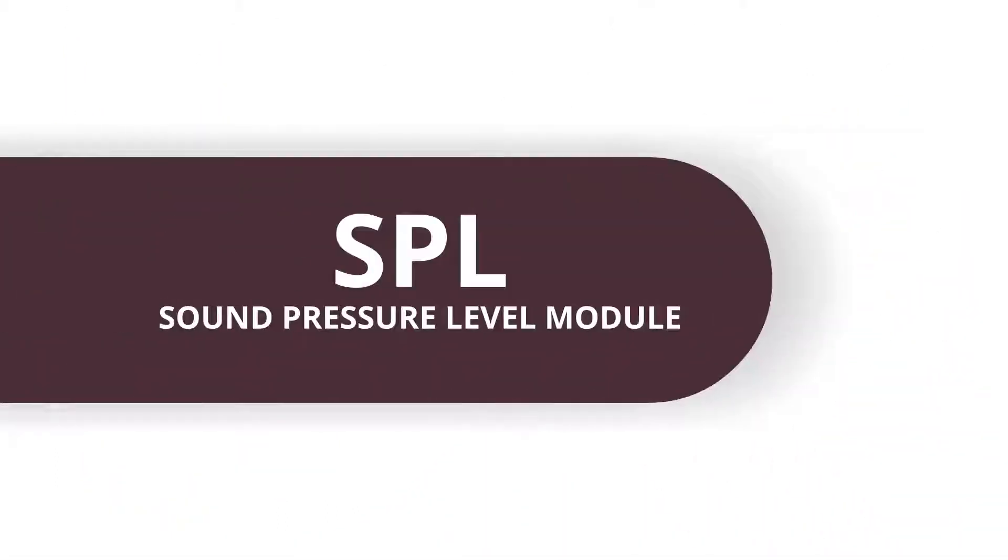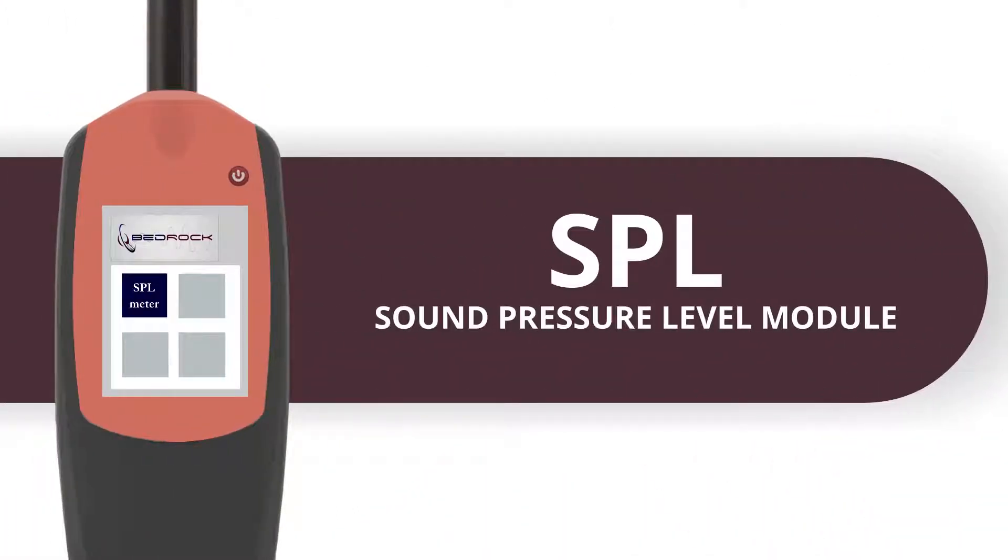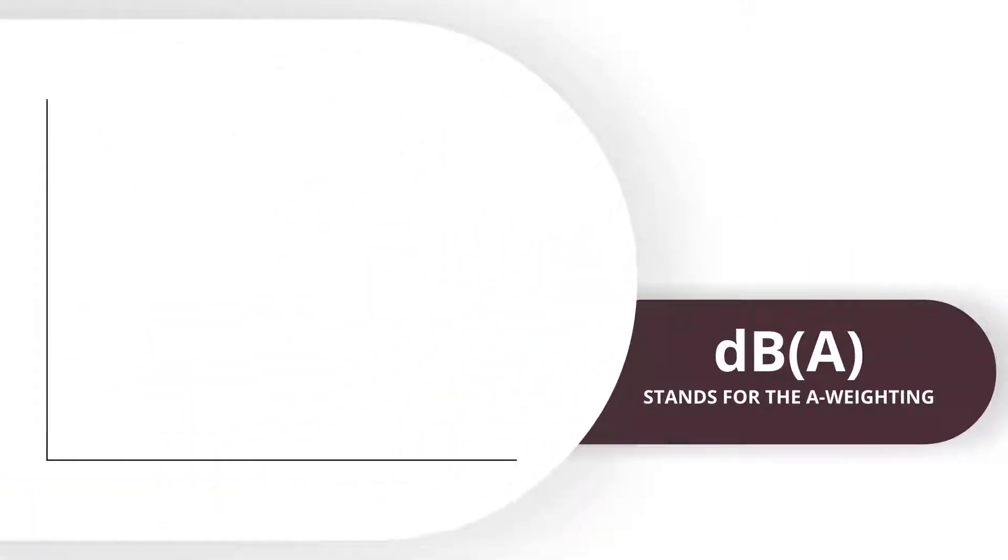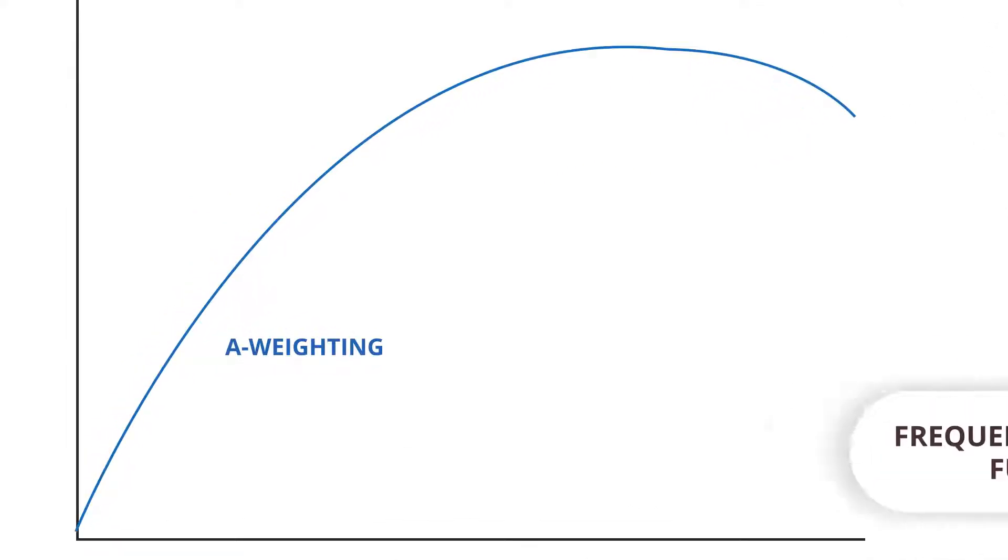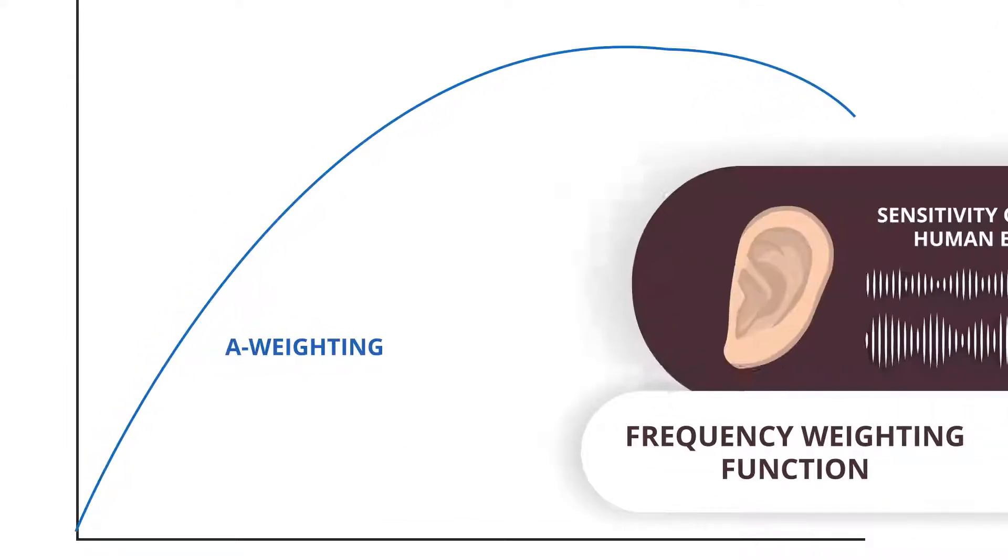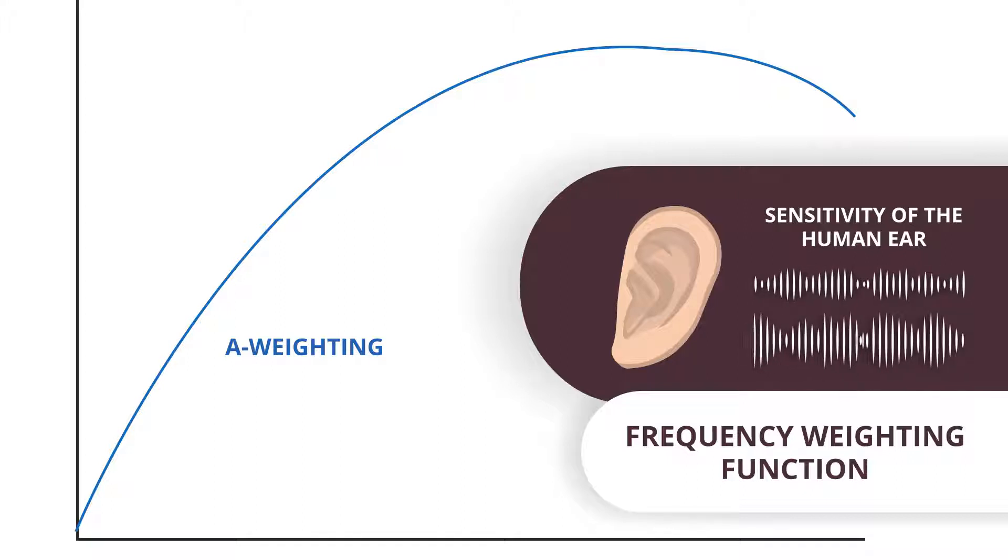The basic sound level meter functions are found in the sound pressure level module, which you can select from the main menu. The most common measure of the overall sound level is dB A. The A in dB A stands for the A weighting. This is a frequency weighting function that makes sure that the sensitivity of the human ear to different frequencies is taken into account.